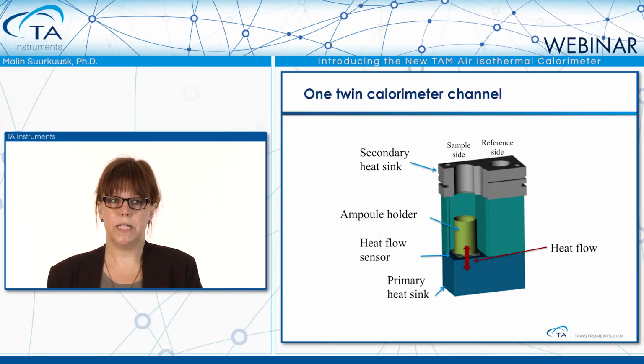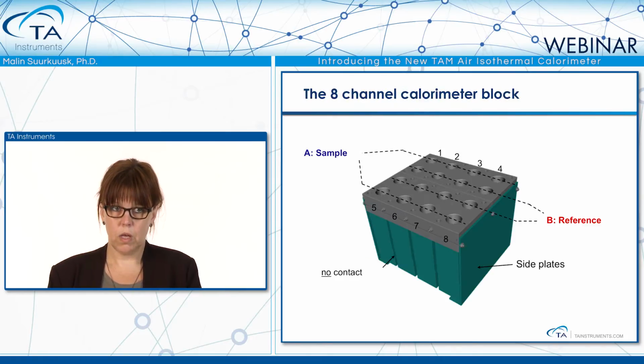In the top, we have a secondary heat sink that will channel away all the temperature disturbances that come from outside. So we isolate the calorimeter, the sample, to just transfer the heat through the heat flow sensor in the bottom. So these calorimeters are then assembled, in this case in an 8-channel block, but also the 3-channel calorimeters will be assembled in a block with 3.